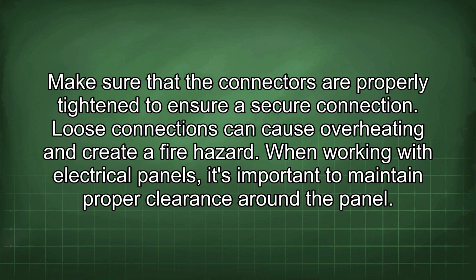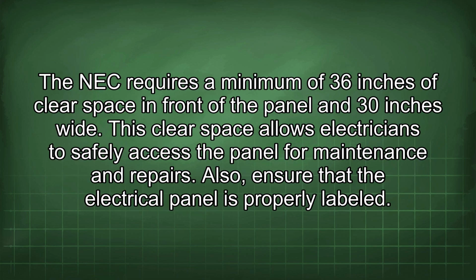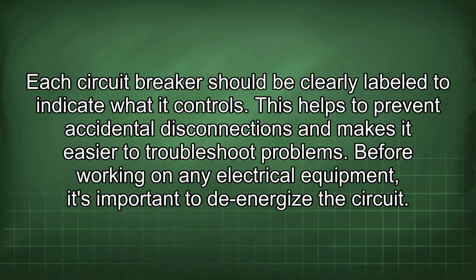When working with electrical panels, it's important to maintain proper clearance around the panel. The NEC requires a minimum of 36 inches of clear space in front of the panel and 30 inches wide. This clear space allows electricians to safely access the panel for maintenance and repairs. Also, ensure that the electrical panel is properly labeled. Each circuit breaker should be clearly labeled to indicate what it controls. This helps to prevent accidental disconnections and makes it easier to troubleshoot problems.